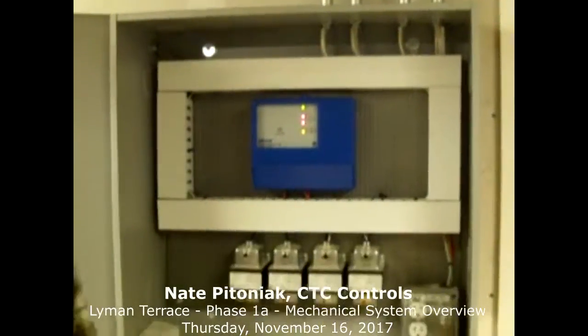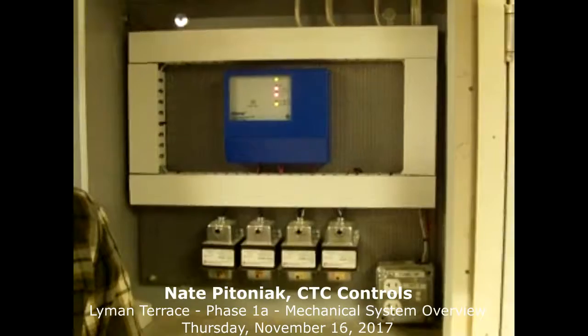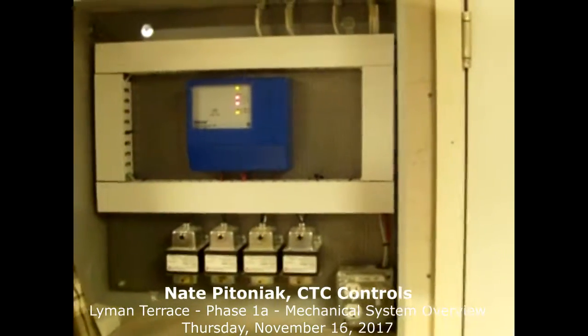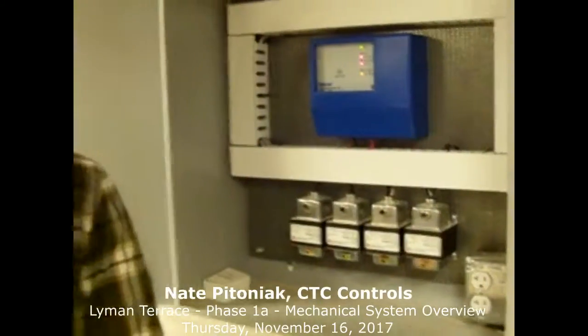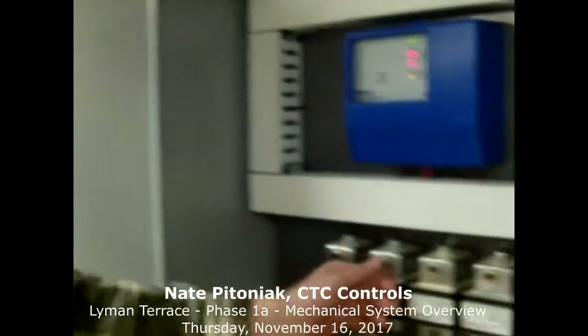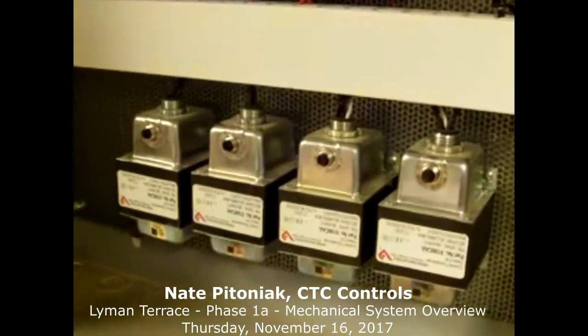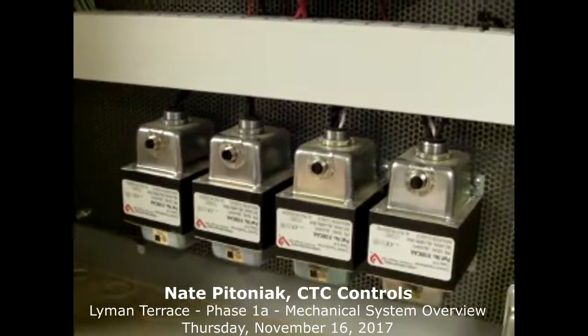And Nate, while we're in this box, let's just say what those four little transformer-looking things are doing over there. Right, this is our power rails for all of the baseboards throughout your entire building here. You'll have a similar setup in each building. If you get a grouping of cold calls, maybe 4 rooms are cold, but the rest are fine, then come down and check your transformers. You can check if it's tripped. These little black dials will pop out. When you reset, you'll hear it click. If it continues to happen, it either means there's a short somewhere in the system, maybe a wire got cut somehow, or the transformer got old, you just need to change it out.